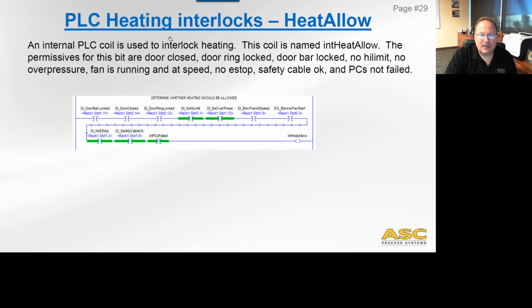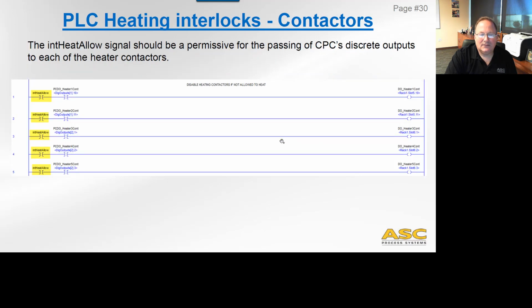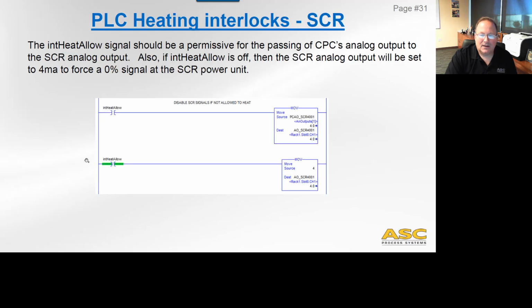So PLC heating interlocks, heat allow. So here's a lot like auto enable. This is heat allow: door locked, door closed, ring locked, no high limit, no overpressure, blower and fan at speed, and then no e-stop and safety cable okay. And in this case, I can have, and PCs haven't failed, and that's going to be int heat allow. And that guy is used as an interlock or permissive for all of the heat contactors, okay? We're also going to use that for a permissive for moving the SCR signal from the CPC register over to the analog output.